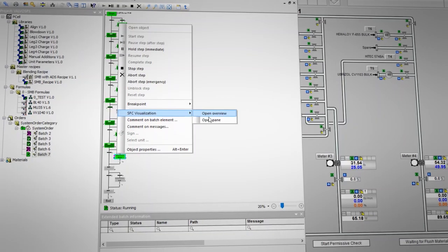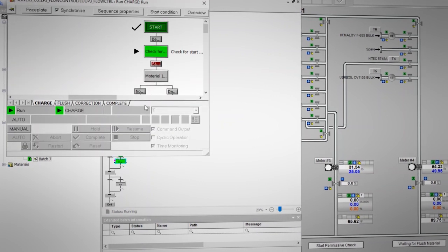process. The sequential function chart is nice because it organizes the logic in a pattern of steps and transitions that you can visualize on the HMI that allows operators to do the first level of debugging, watching the interactions or finding out what's holding them up on it without getting an engineer or maintenance involved.